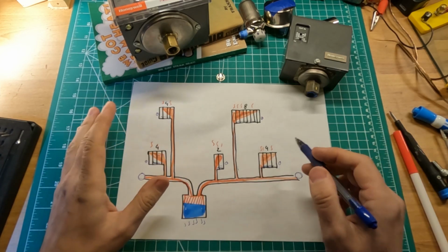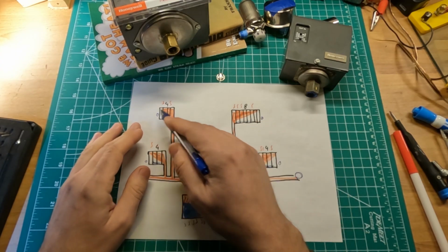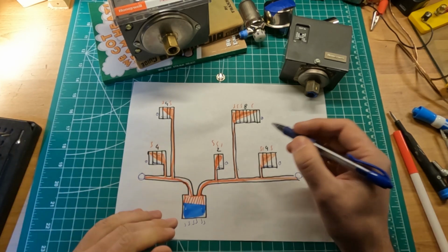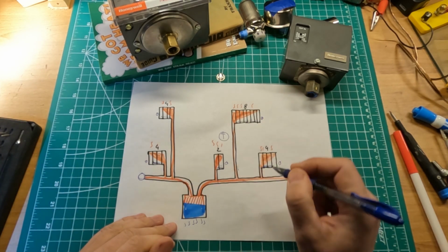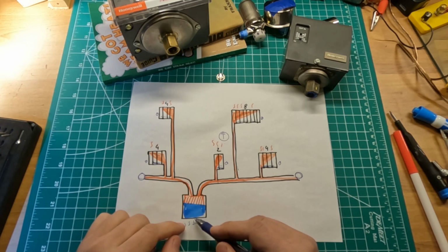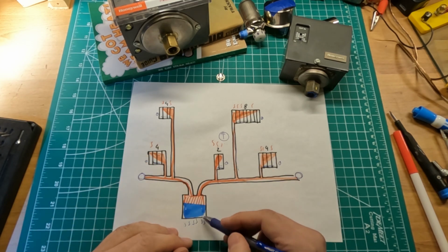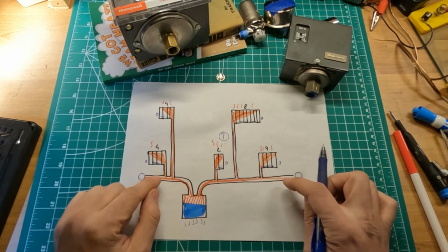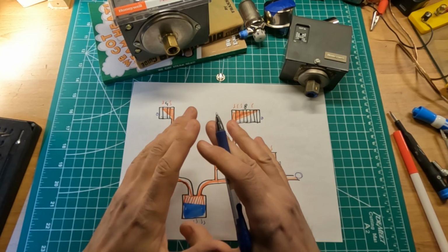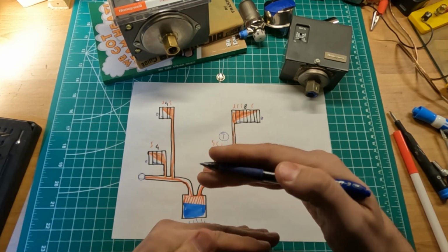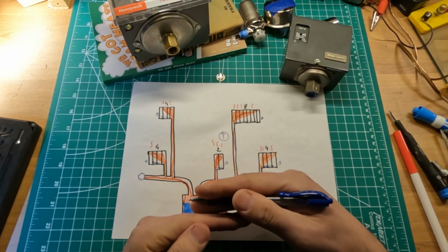That said, let's assume that we have partially filled radiators, as in the vents have closed, and yet the thermostat, let's say we have the thermostat somewhere here, is still not satisfied. The room has not heated up enough, so the thermostat keeps on calling for heat. Of course, the boiler doesn't care. If it's being asked to produce more steam, it keeps on producing more steam. The problem is that because of the closed vents, the steam has nowhere else to go within the system. So the pressure inside the boiler builds up.